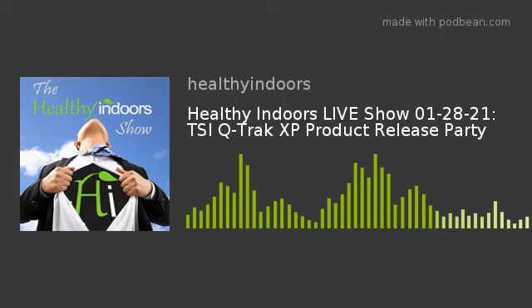So, I have one last question before we do a wrap up, because we're approaching our wrap up time. One question is that VOCs are one of the hardest measurement conditions out there. Most of the other ones are very dead on in terms of, okay, these are my numbers, but there are so many things that could be giving me VOC. So what's a recommendation in terms of how long I should be in an environment or near something to know that I have actually determined the VOCs being created in that area? Do I need to stay there for 2 or 3 minutes, or am I getting readings within 30 seconds for this type of device?